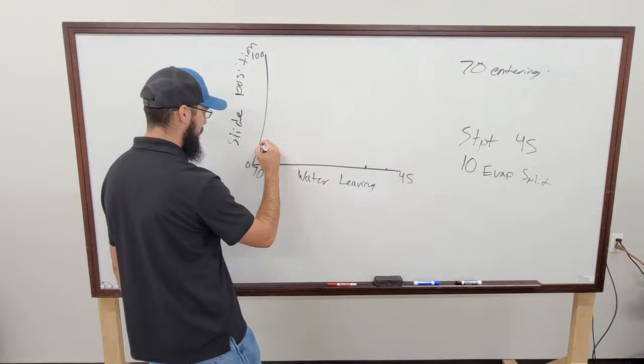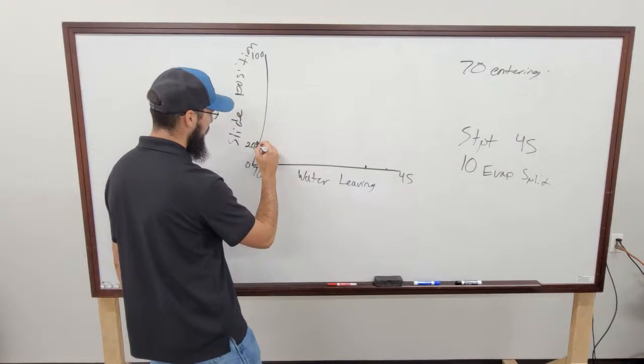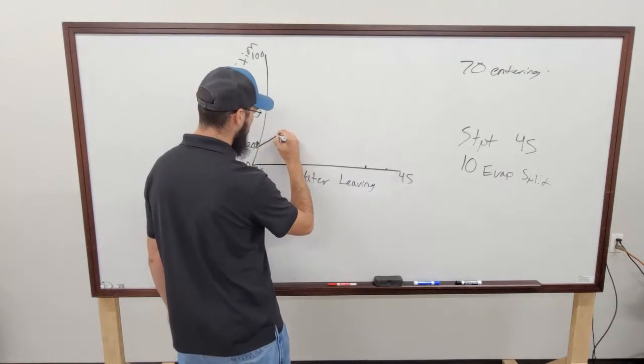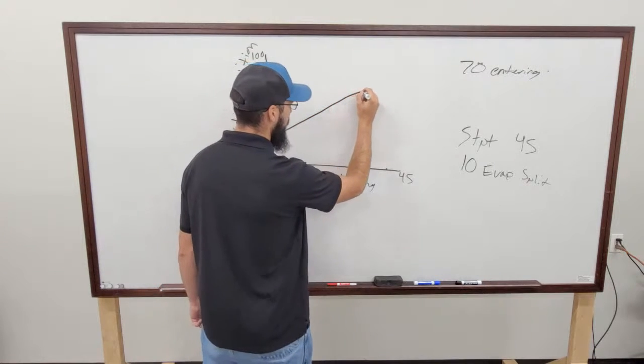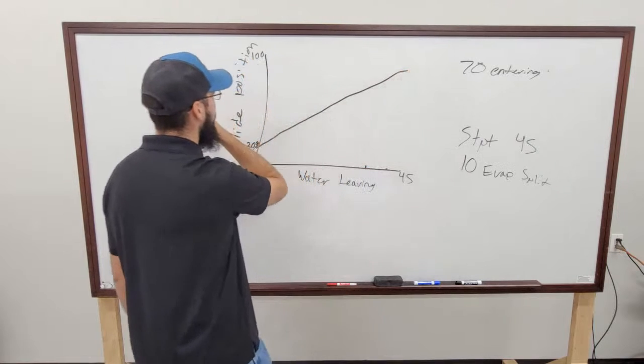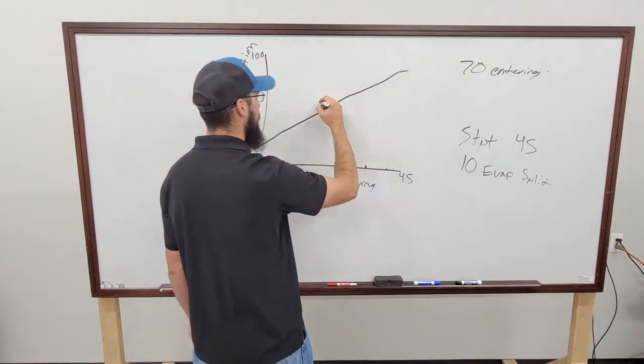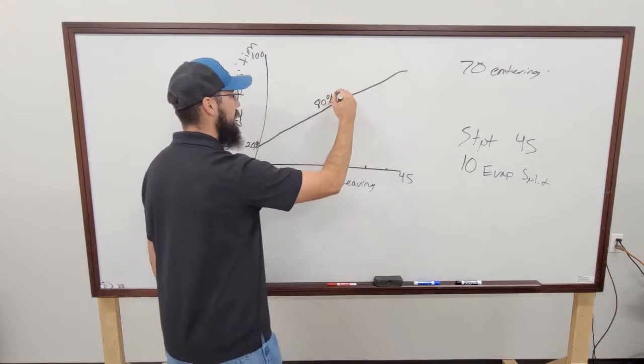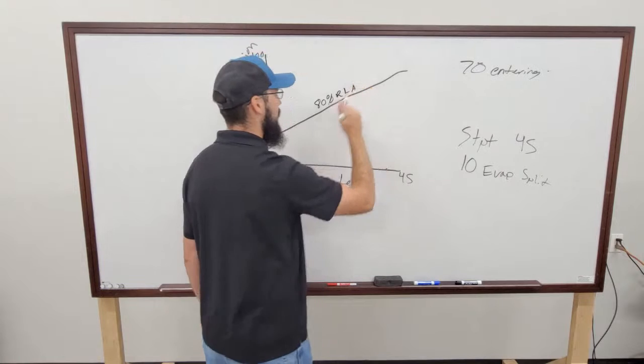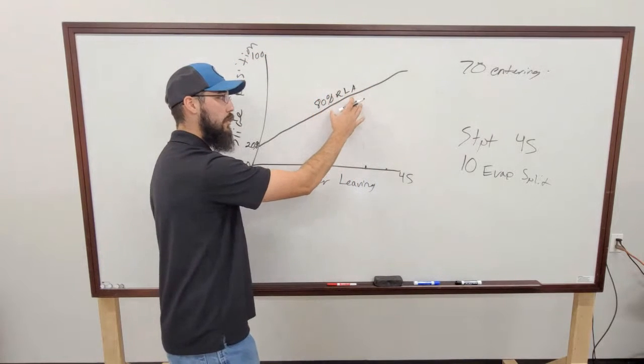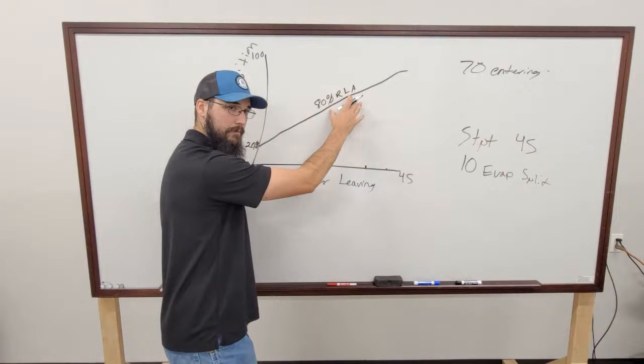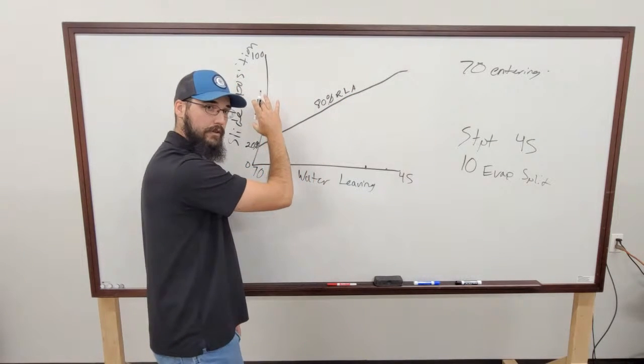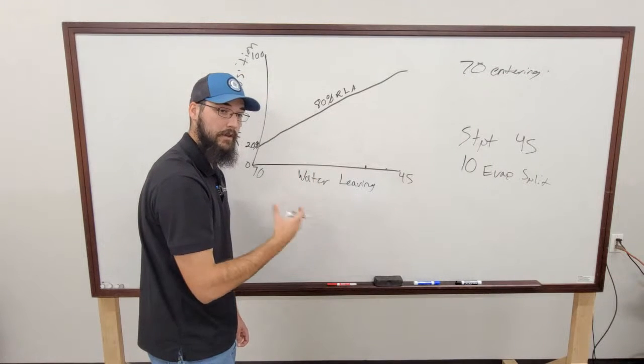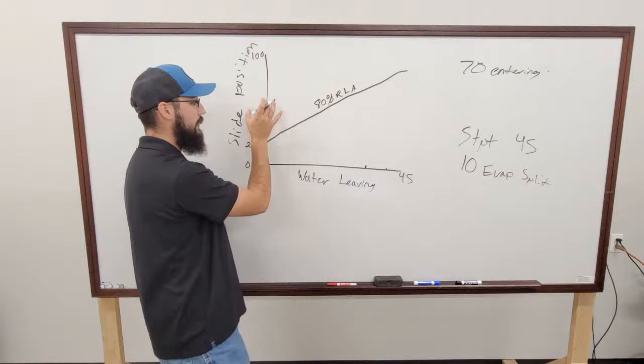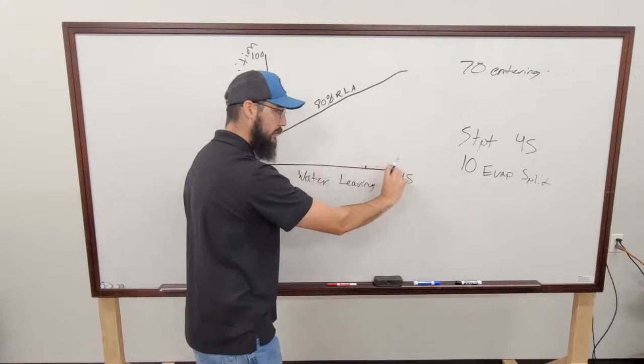We would come up, say probably, I think the minimum would be probably like 20% slide. And as our water temperature drops and we get to 45, you're going to see your slide position increase. But we maintain an 80% RLA the entire time. So the motor load maintains the same, but the slide in the compressor, or the speed of the compressor, depending on what style you're working on, is slowly increasing as our water decreases.